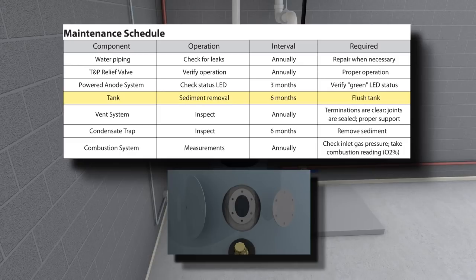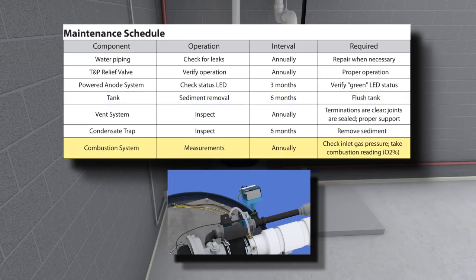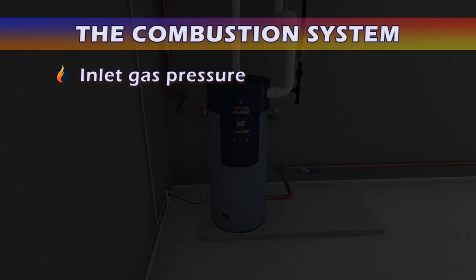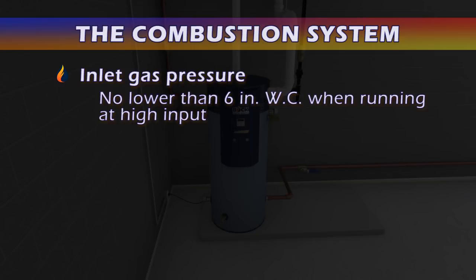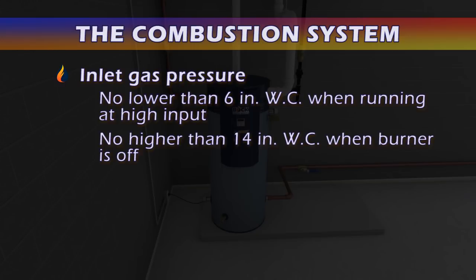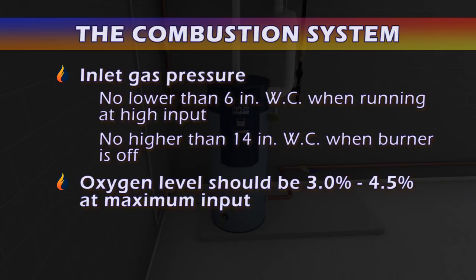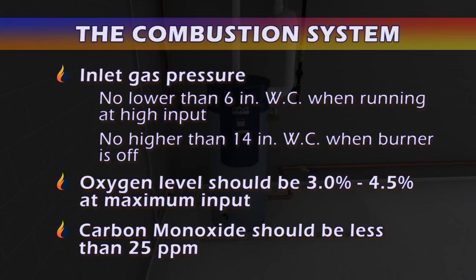Flush tank. Open the handhole and visually inspect the inside of the tank for sediment buildup twice a year. Drain and flush the water heater to prevent lime and iron buildup, which can lead to premature tank failure. A commercial descaler may be required. Check combustion system. The combustion system must be checked once each year. The inlet gas pressure must be no lower than 6 inches of water column when running at high input and no higher than 14 inches of water column when the burner is off. At maximum input, the oxygen level should be between 3 and 4.5%. CO should be less than 25 parts per million.